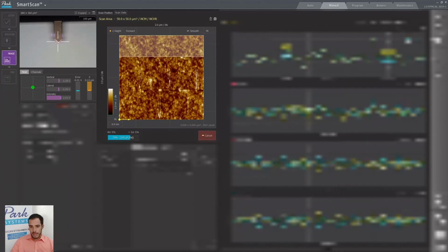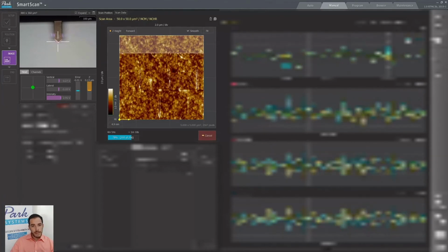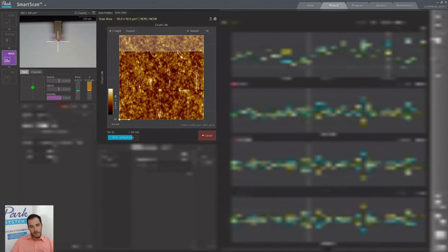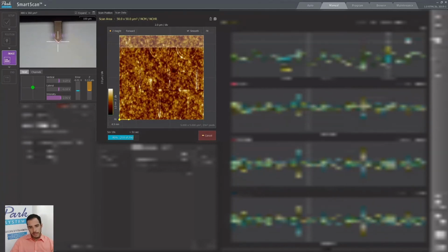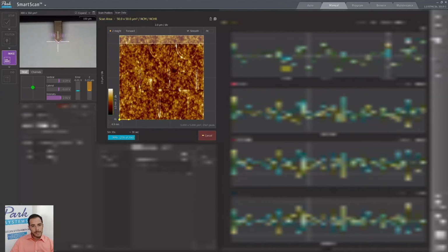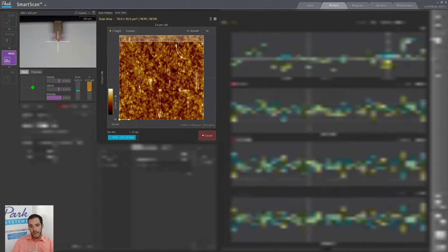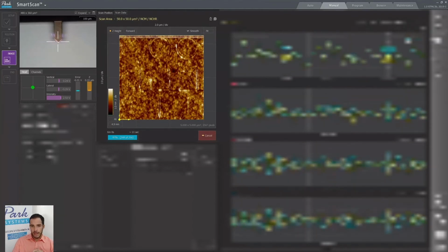The left one is not as clear as the right one, but it's because of the amount of force we have just applied. And we can finally start seeing the circles in there. You can also see the six grooves that are formed around, six because there are two per circle, right? And we just have to wait a couple of seconds before we can proceed to analyze our image in our analysis software, which is called XEI.